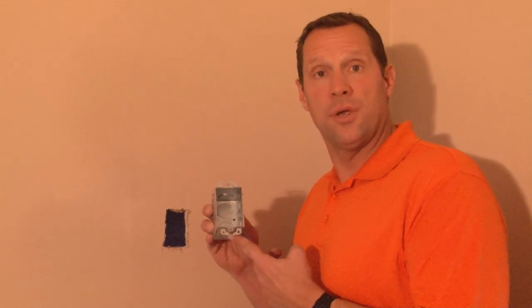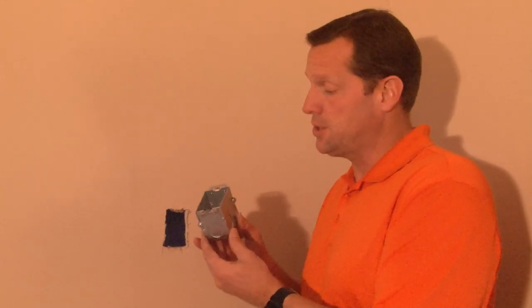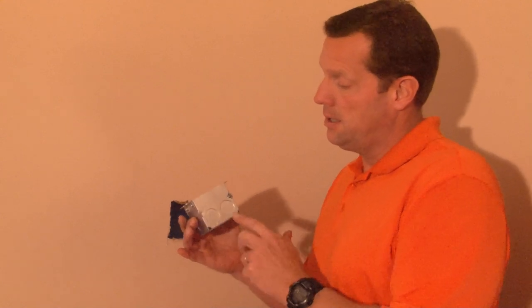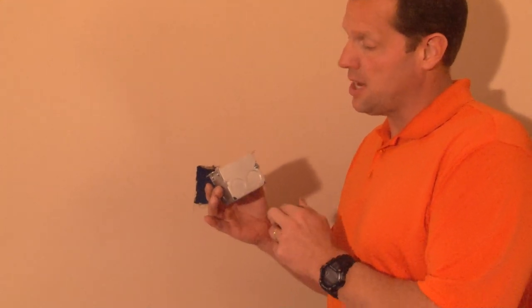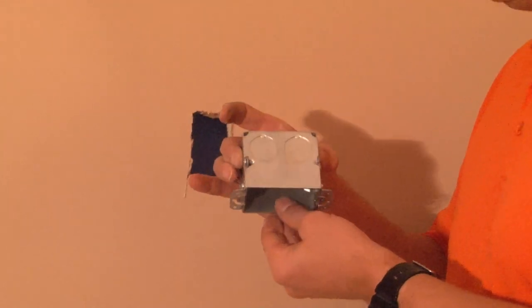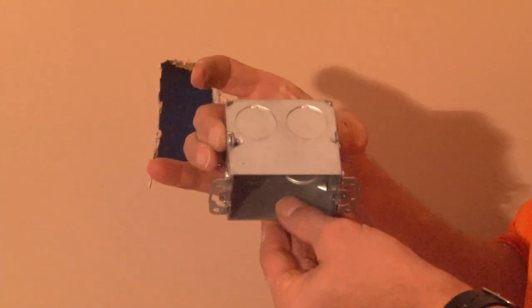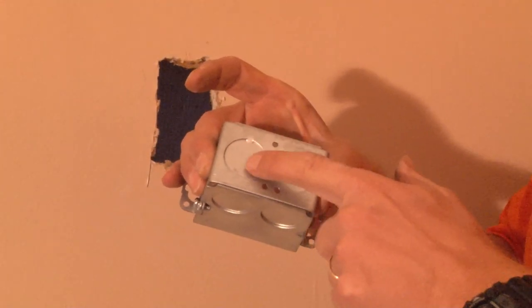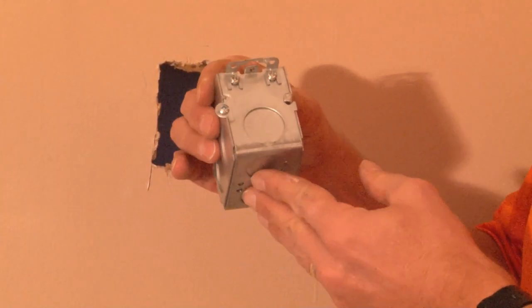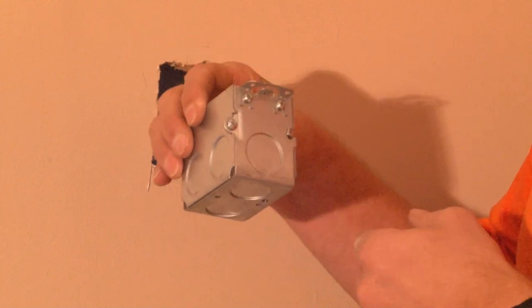Part number G601 3/4 is a two and a half inch deep switch box that has two 3/4 inch knockouts on each of the sides, two 3/4 inch knockouts on the bottom, and one 3/4 inch knockout on each end.